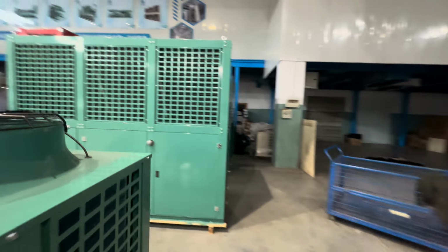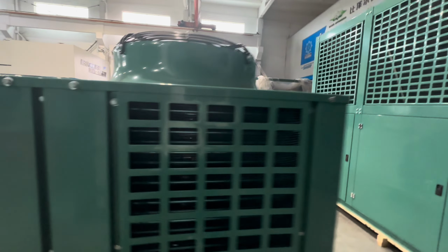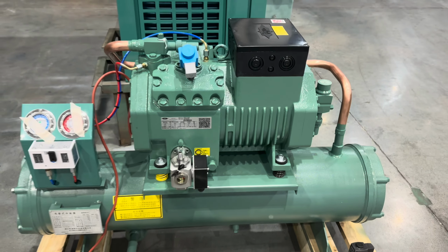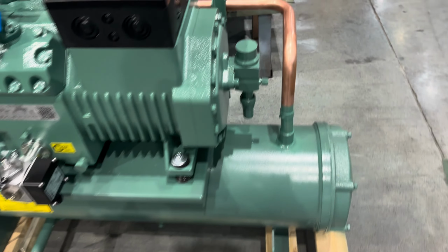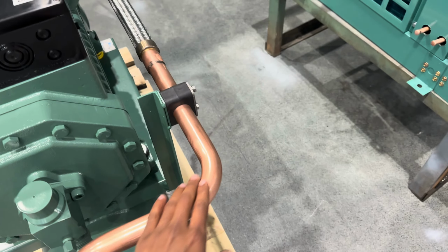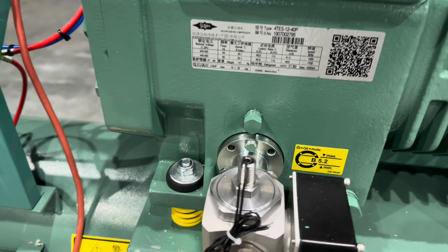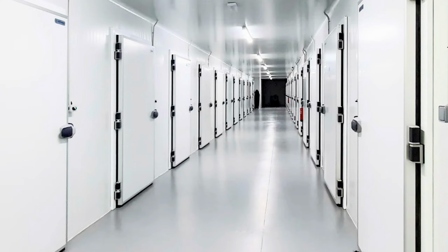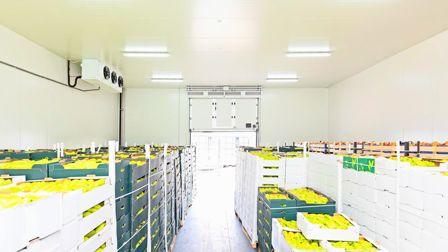So that's about this compressor. The disadvantages are the price, which is a little bit higher, and that it requires maintenance. You need to change the oil about once a year, and you need to check it. So the maintenance and the price are the disadvantages. It's best used for large and small cold rooms, and also for ice makers and meat.